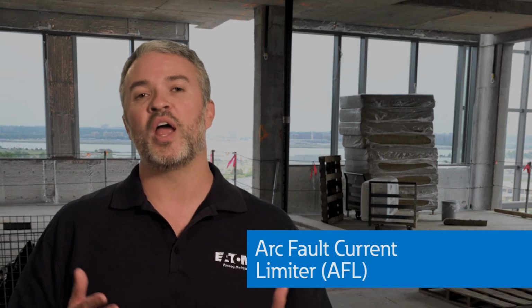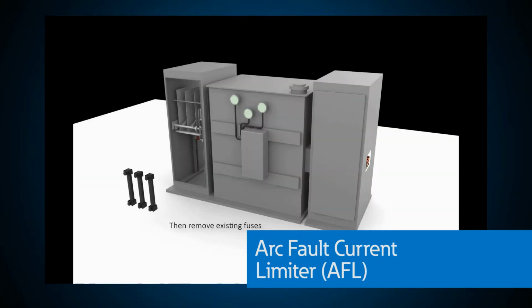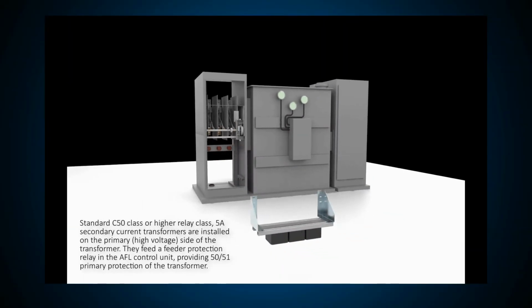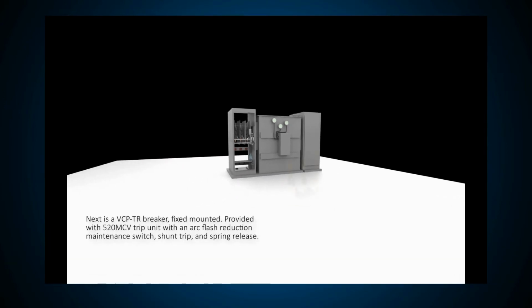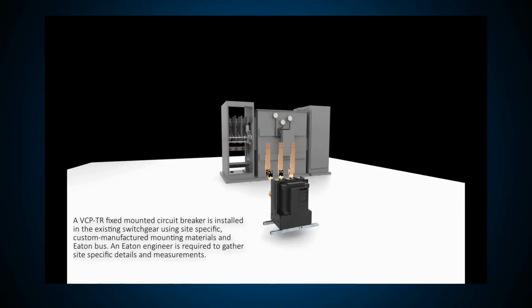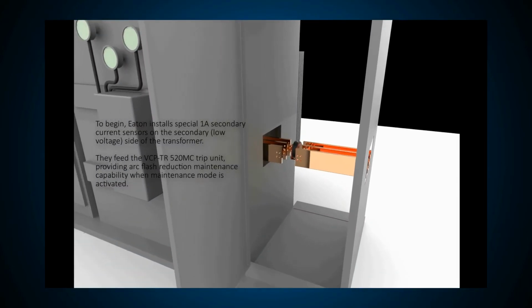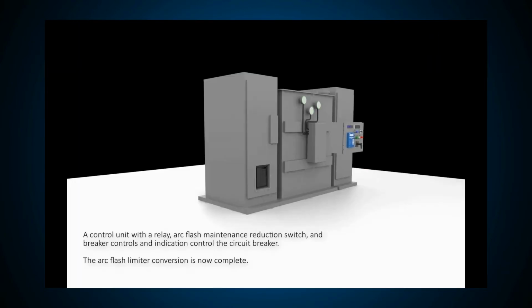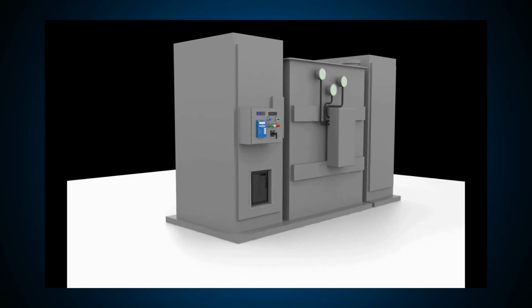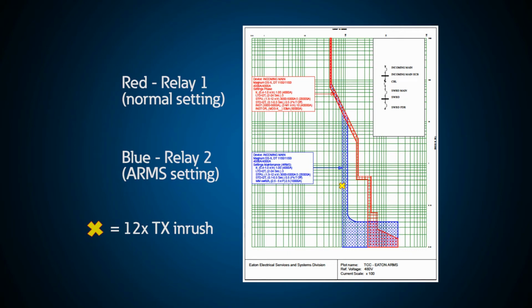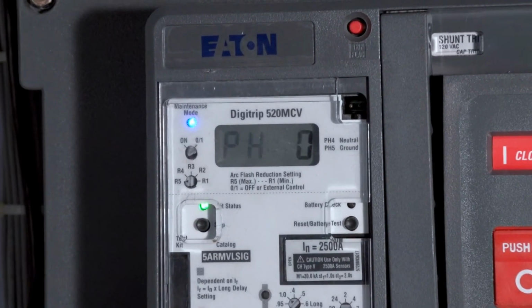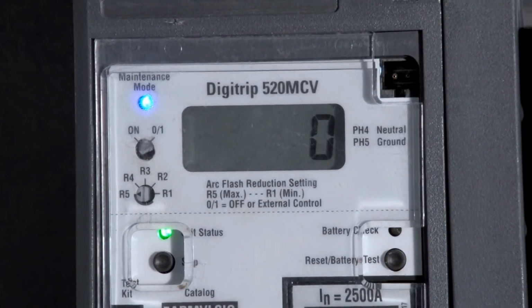One great option to reduce this level is the Arc Fault Current Limiter, or AFL. For this demonstration, we have replaced the typical medium voltage primary fuses protecting this transformer with a medium voltage vacuum circuit breaker, and we installed current transformers, or CTs, on the secondary of the transformer and added another protective relay. Since the breaker has two protective devices that can trip it, one is set as it normally would to overcome the 12 times inrush current for the transformer, and the other is connected to the transformer's secondary CTs. Using an ARMS setting, it will trip without delay during a fault condition.